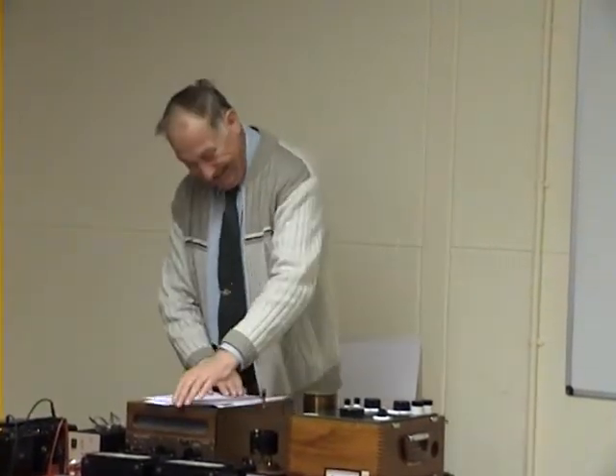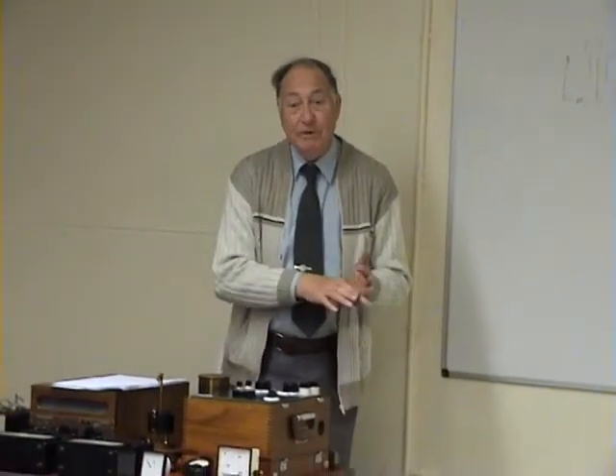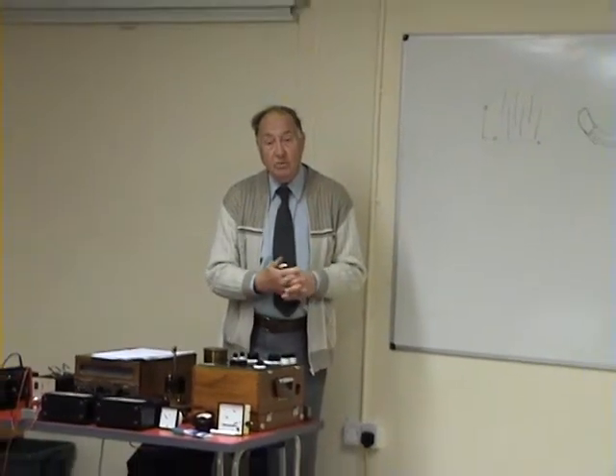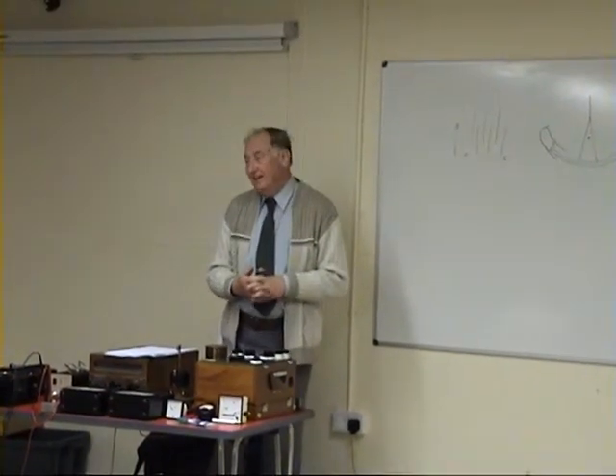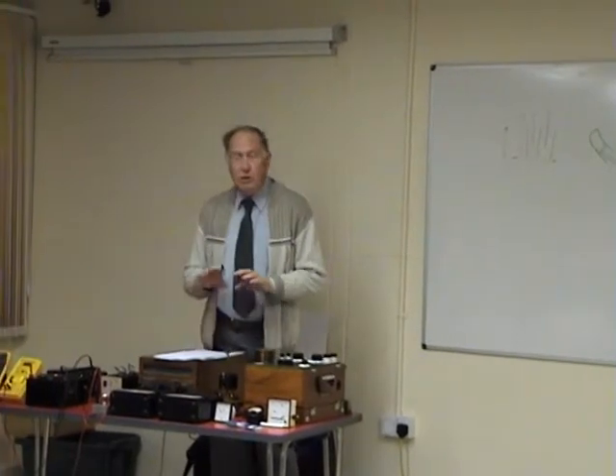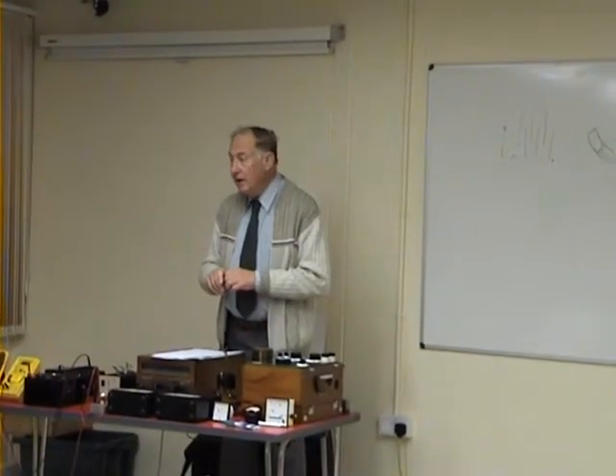Using large quantities in the electricity supply. Absolutely. An interesting point, as was demonstrated once accidentally at Emerson, I was only an observer. Current transformers like to be loaded. They have to have a secondary connection to them, and if they don't have one, they tend to catch fire. It must be shorted. Oh, yeah, shorted. They tend to catch fire if not. So you're unlikely to come across that in amateur radio.